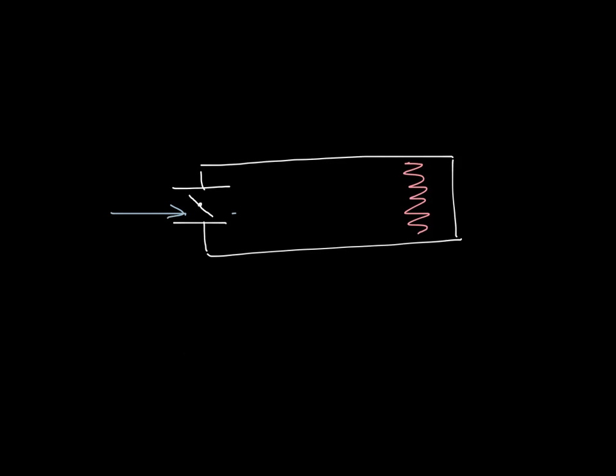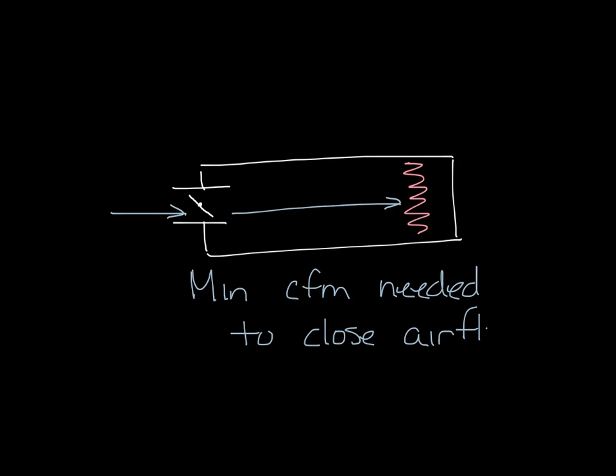And the damper is kind of at a minimum position because it's looking for the heating CFM. In a box with electric heat, you have to have enough airflow to close an airflow switch so that the heater will energize. So if you oversize the box and you can't get enough airflow to make the airflow switch, the heater won't energize.